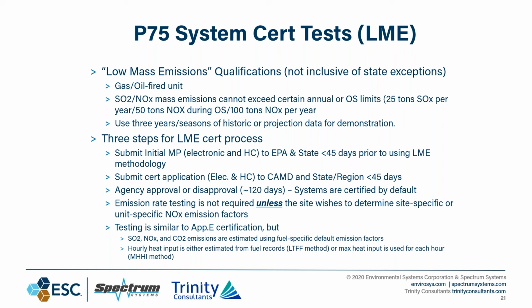Or we had 5 steps for other types of CEMS. Here you got 3. You submit your initial monitoring plan to the region and state. You submit your Cert app, both of them, 45 days or earlier. And then the agency can approve or disapprove around 120 days. Your systems are certified by default while you're waiting.